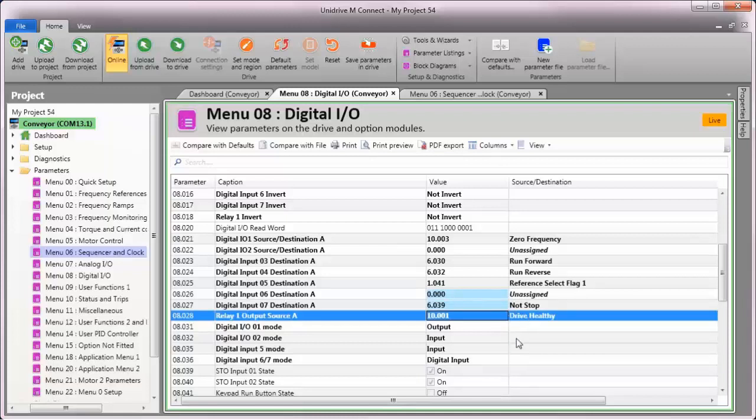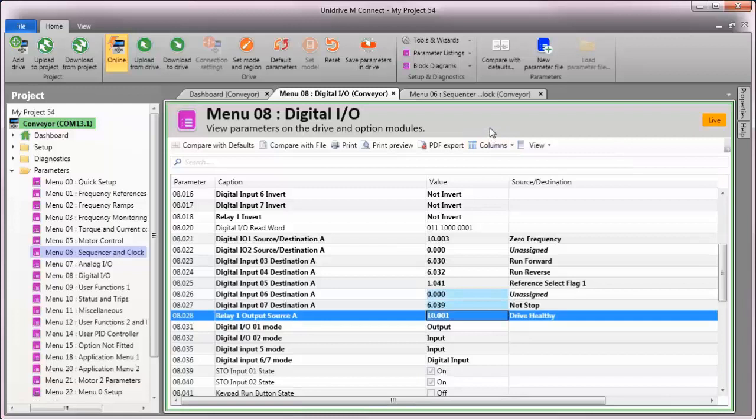Next, we'll need to enable sequencer latching so that when I remove the run forward or run reverse signals from the control terminals, the motor will continue to run until I wish to stop it using digital input 7 that we've just configured.